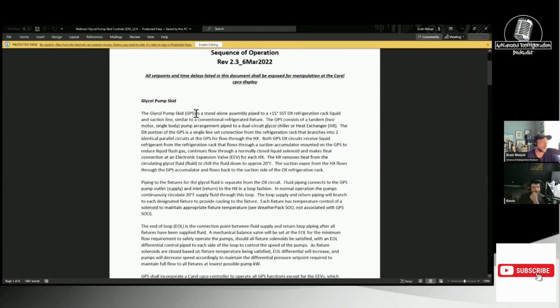So I finally found what we were looking for. The glycol skid is standalone, pipe plus 15 suction SST. My other question is, because sometimes this gets overlooked - if on these racks you don't have a constant suction pressure, was that something you were able to scope out? Were they able to tell you that it's a constant suction? Because obviously the valve's going to hunt like a bastard if your suction's all over the place, right?